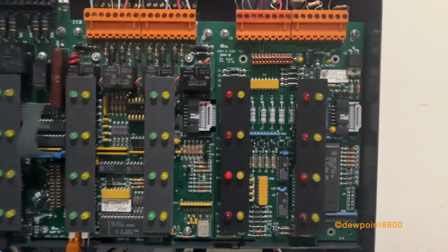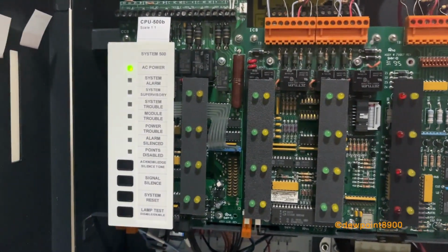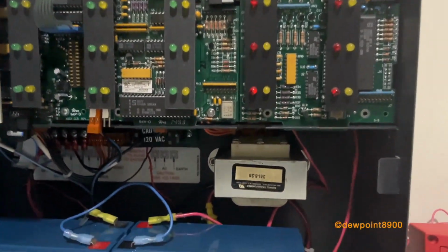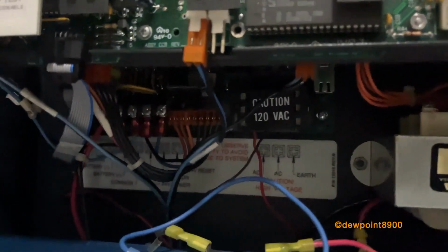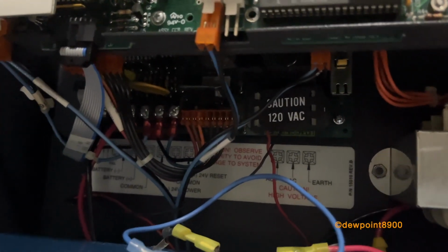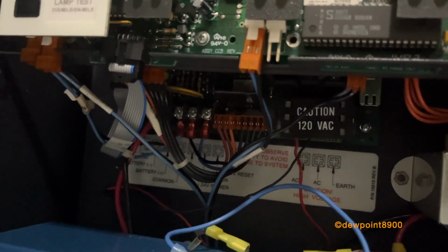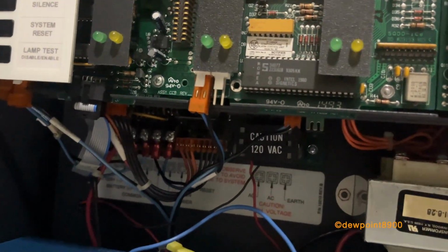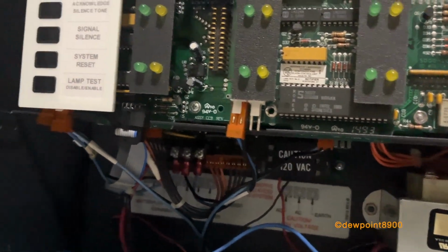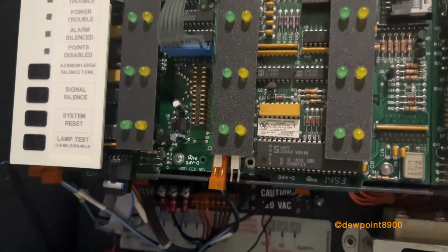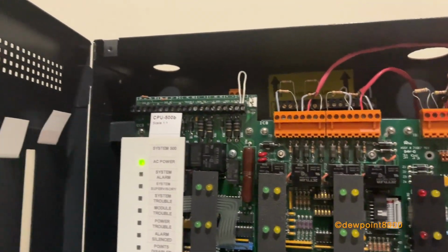These 2 cards connect via ribbon cable back to the CPU, and that's how they are controlled and supervised. Right there's the transformer, and underneath all these cards is the MPS24B power supply. It powers the system, and it's also responsible for powering any signal circuits or external devices like annunciators. All these little orange connectors there are signal harnesses to power all of the signals.